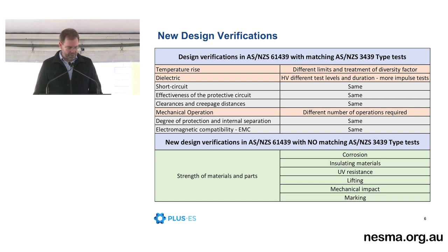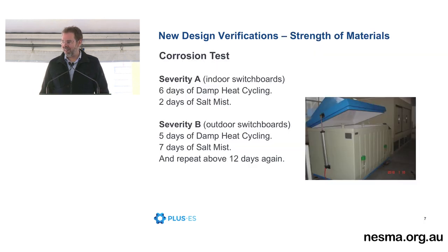I'll just go through the green section. So we've got corrosion testing, and it's simulated corrosion. I don't know how long the period is that they're simulating, but effectively it's a combination of a damp, humid environment, and then they put it in a salt fog or a salt mist chamber, which accelerates the corrosion of ferrous metals. There are 2 severities, severity A and severity B. Severity A is for the indoor switchboards, but if you want to put one outdoor and have a corrosion verification, then you need severity B.